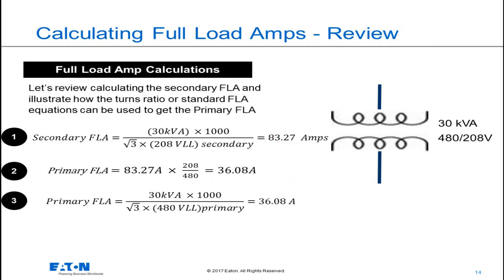So here we're going to calculate the full load amps on the primary and secondary of a 480 to 208 volt 30 kVA transformer. We're going to leverage the equations we just derived.